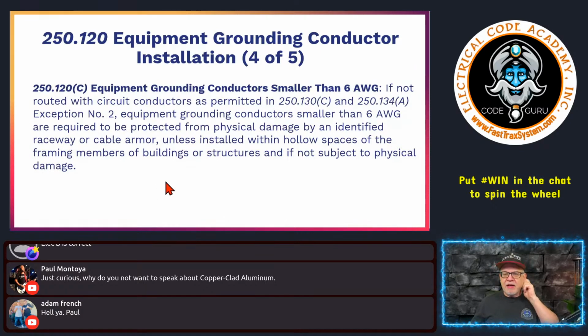And that covers that. And 250.120(C), what about those equipment grounding conductors that are smaller than 6? Okay. Now it says equipment grounding conductors smaller than 6, if not routed with the circuit conductors as permitted in 250.130(C). And that is an allowance. There's a unique allowance where you might have a system that doesn't have an equipment grounding conductor in it, and then you'll get an allowance to run a single equipment grounding conductor that is not with the circuit conductors. This is very unique. This is where you have older systems. It gives you some options.